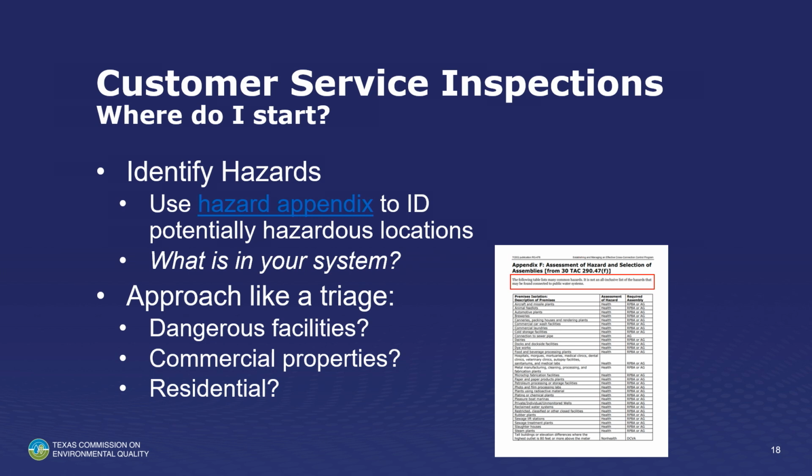So customer service inspections, where do I start? Well, I start at the meter and go on. I start looking at backflow assemblies. They have hose vacuum breakers out there. And if they've got backflow assemblies, I want to see the BPAT forms. Did these get tested? If they did, I want to see them. Then I want to match up the serial numbers on it. A lot of cities require us to, they want to know the meter number, the size, the line going in. Fortunately, a lot of stuff now, they're doing PEX. If we've got any solder joints, we're going to have to do a lead test.